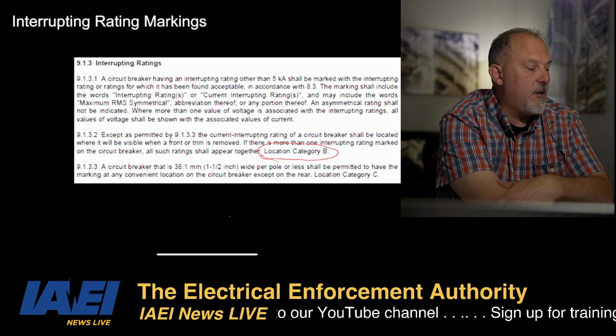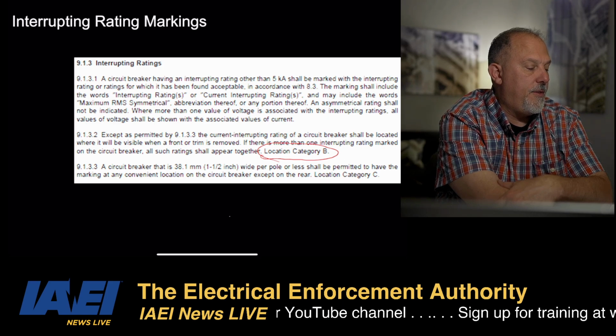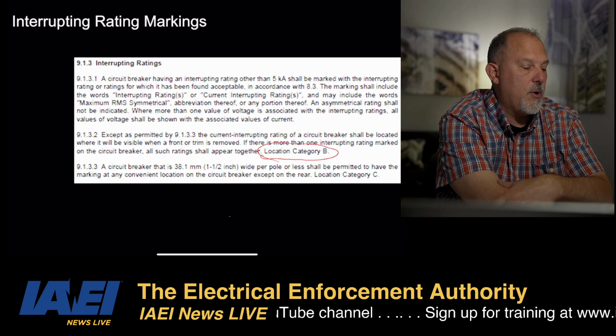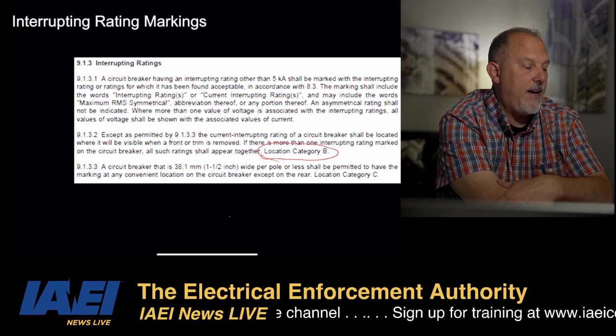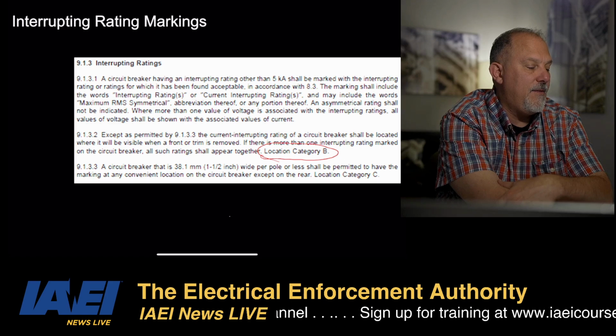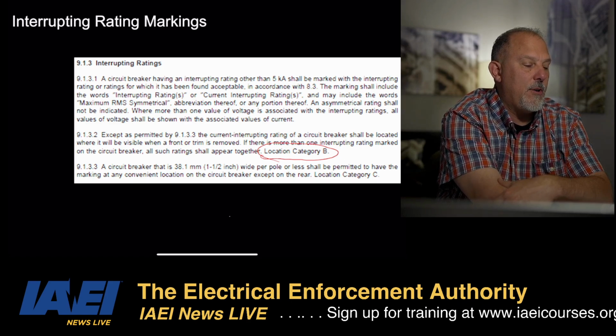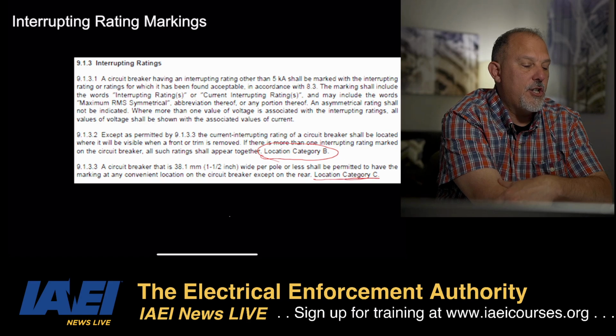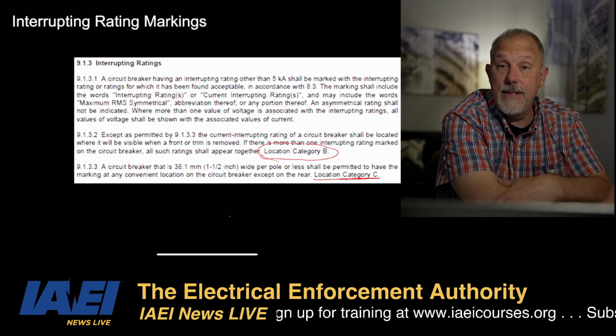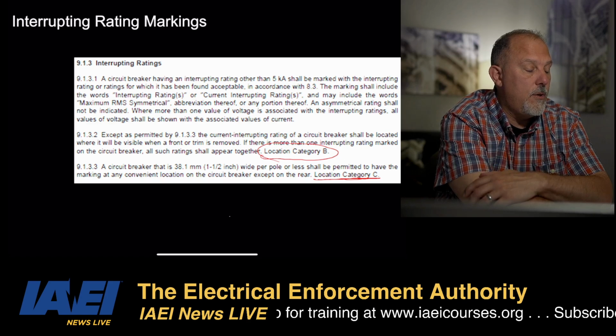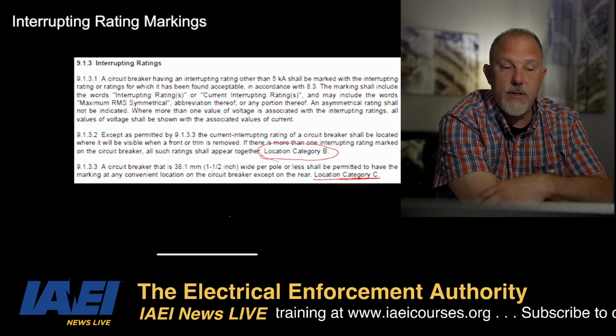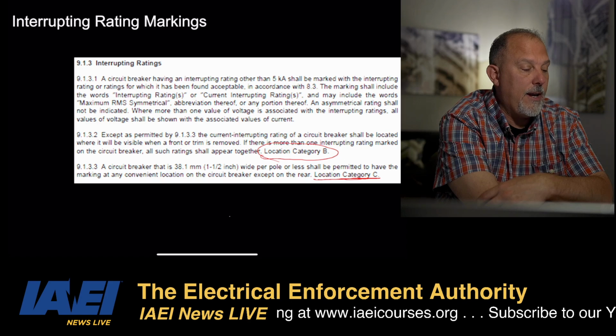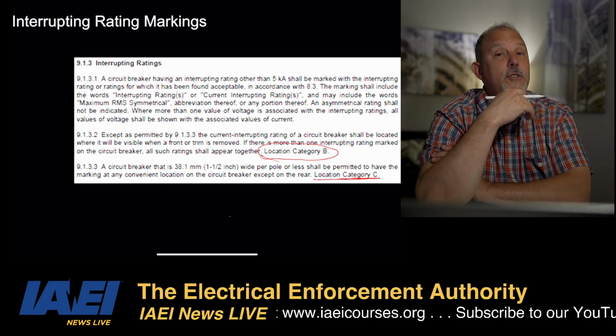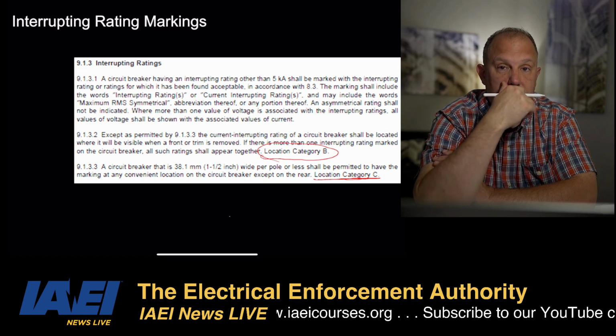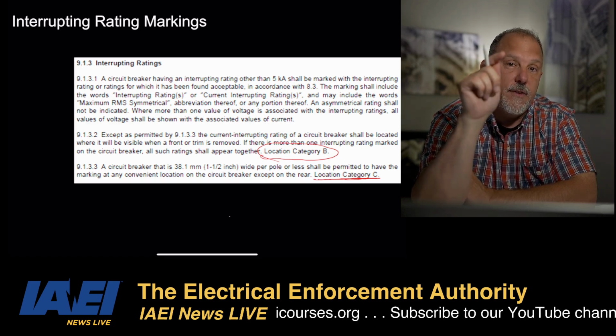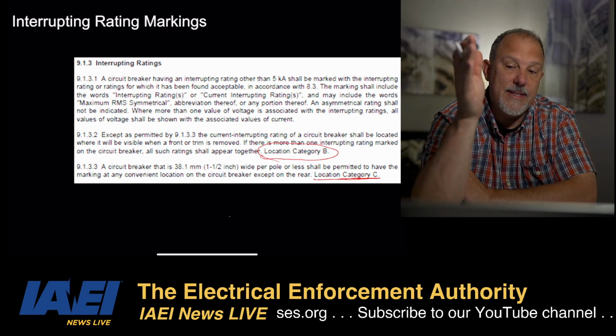9.1.3.3 says a circuit breaker that is 1.5 inches wide per pole or less shall be permitted to have the marking at any convenient location on the breaker except on the rear. And that is location category C. So you may see that some of those, and it says 1.5 inches wide per pole, are going to probably be your smaller circuit breakers. And I'll bet you'll find some manufacturers put those on the side.